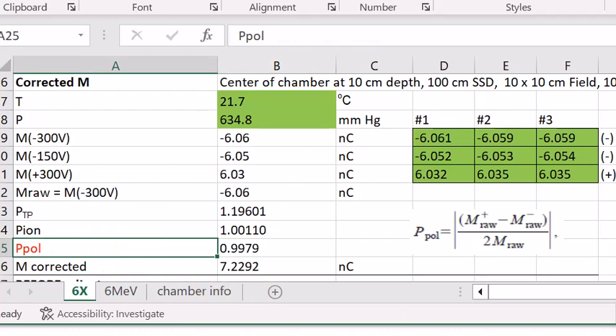Last but not least, TG51 states it is unlikely that the polarity correction factor is more than 0.3% different from 1.